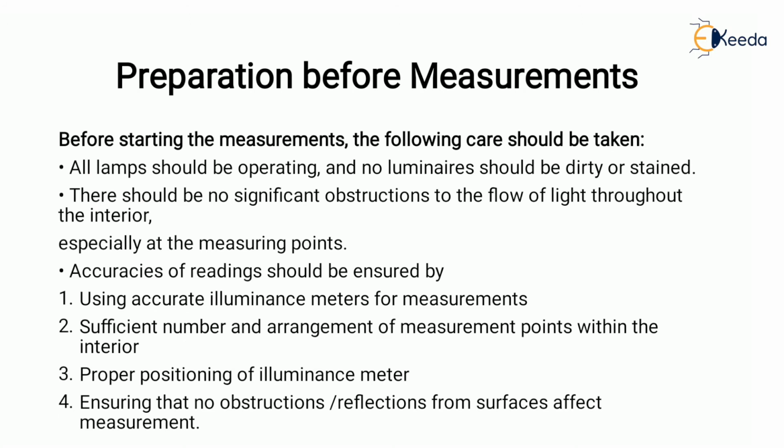Now let us see what are the preparations to be made before measurement. So these are all lamps should be operating and no luminaires should be dirty or stained. Next is there should be no significant obstruction to flow of light throughout the interior, especially at the measuring point.